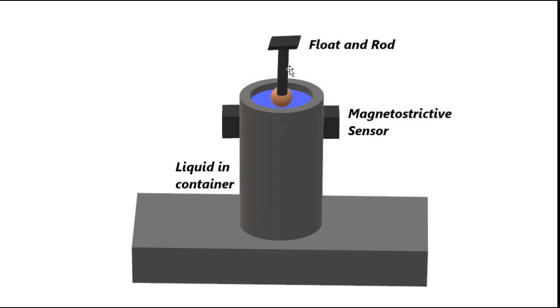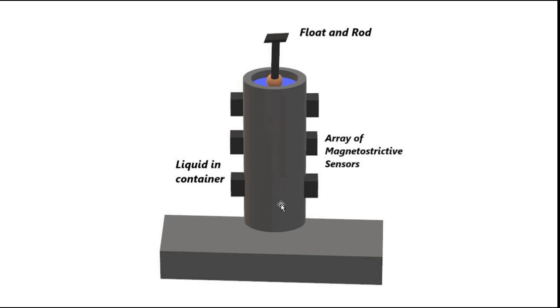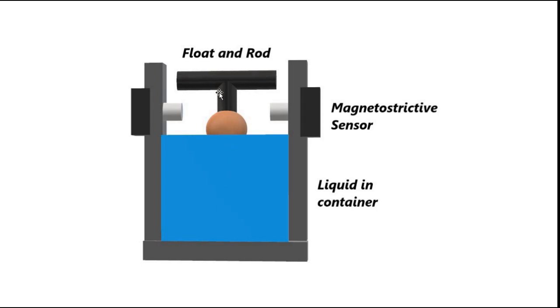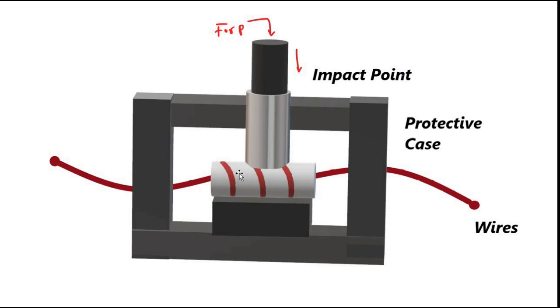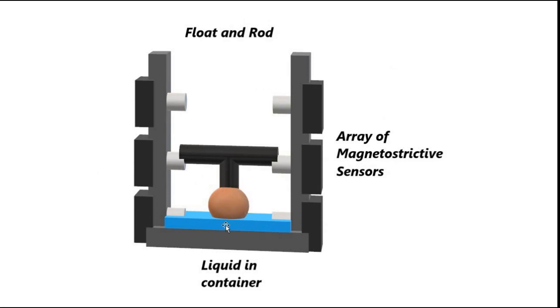In industrial systems, whenever the level goes beyond a danger level we want to send an alert signal, or when it falls below a certain level we need an alert — for those purposes a single sensor suffices. When we need continuous tracking — knowing the level at every time instant — we connect a series of magnetostrictive sensors. As the liquid level goes up and down, the float goes up and down, and the rod strikes the impact points of successive sensors, triggering them.